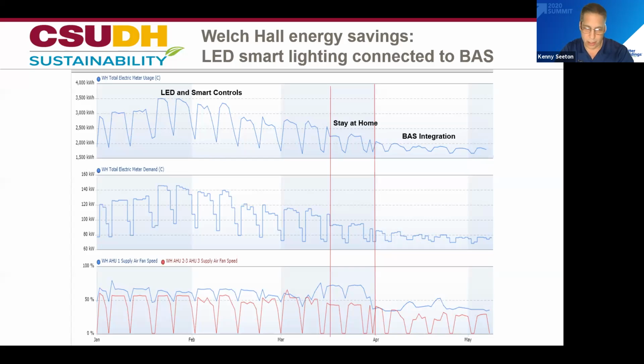So the top is our kWh, how much electricity we're buying. The middle is our kW demand, which will be important when we add batteries and solar to this building. The bottom shows our fan speed, because when we tied the lights into the building automation system, the static pressure dropped way down and fan speeds were able to turn way down. In the beginning we had issues tuning and commissioning it, but at the far right it got nice and stable, and it stays that way now.